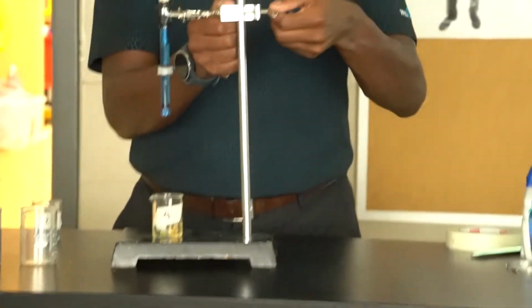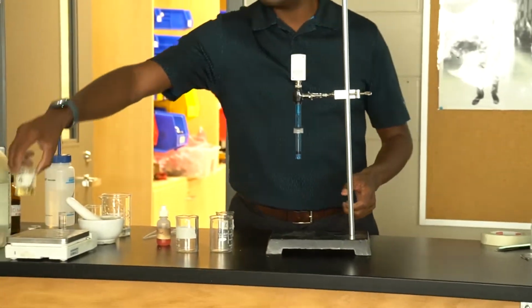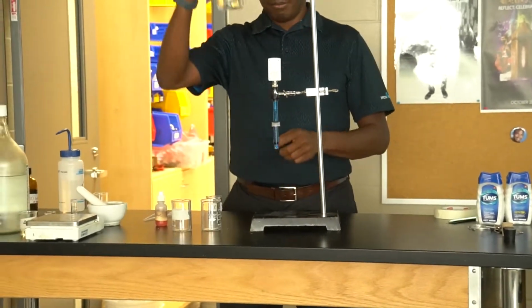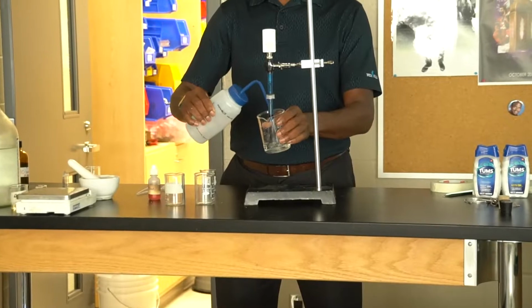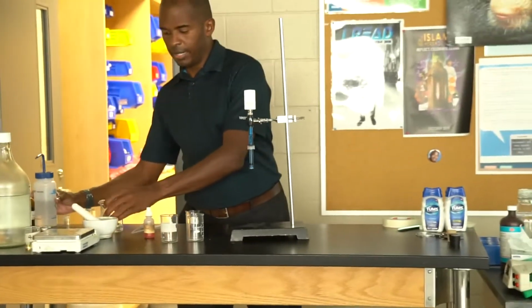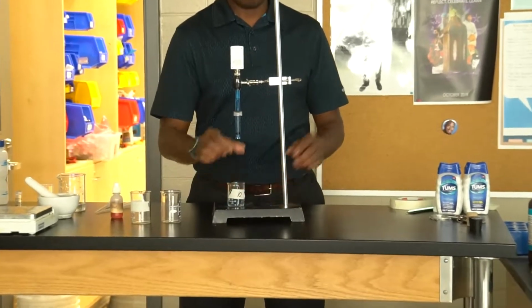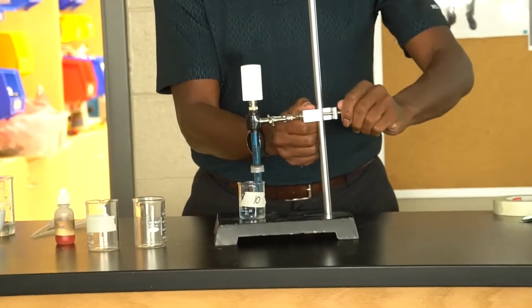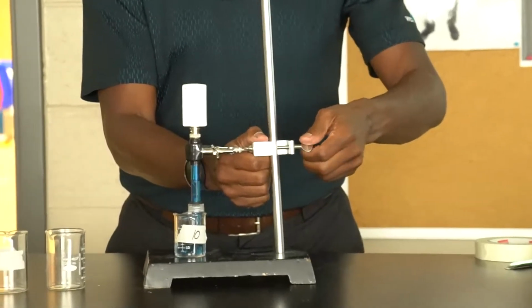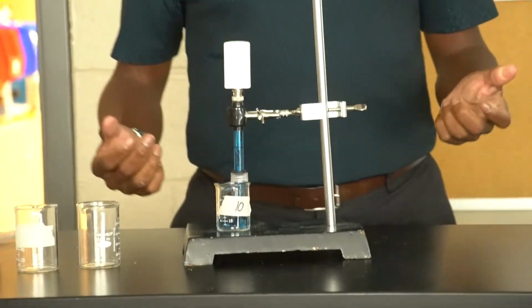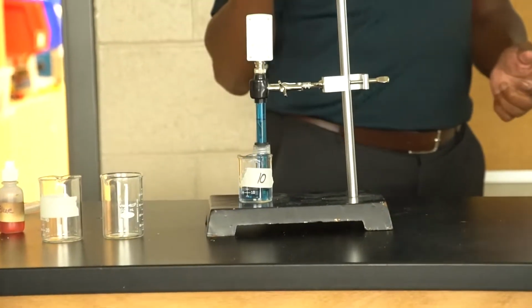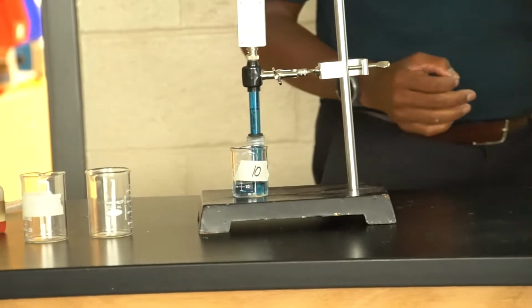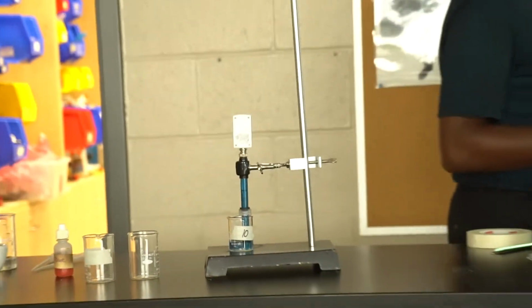I come back over to my pH sensor. I lift it up, I lift it out, move my pH 4 out of my workspace. I'm going to go to my cleaning beaker. I'm going to rinse it off. And then I'm going to go to my pH buffer 10. So this is important. We talked about acids and bases already, and we used indicators, we used pH paper. So this is another technique we can use for measuring, but with a probe, you have to tell the probe what the correct values are, and that's why we use these buffers. We have to give it 2 points, so then the computer application can use an algorithm and determine the pH correctly. So now it's been sitting in 10 for a while.